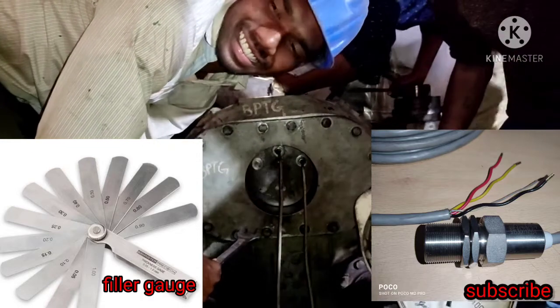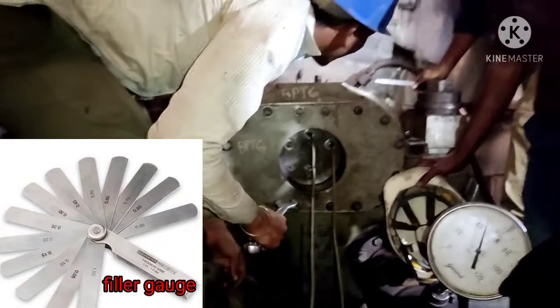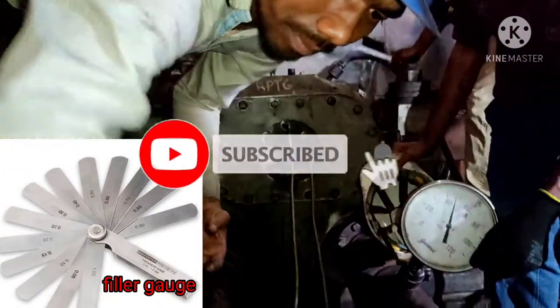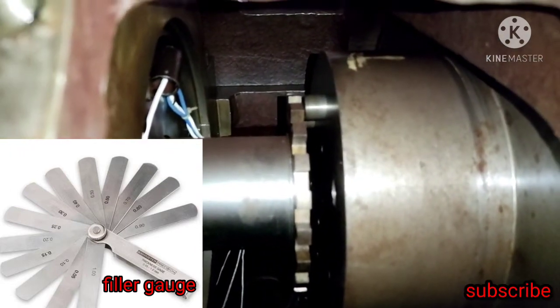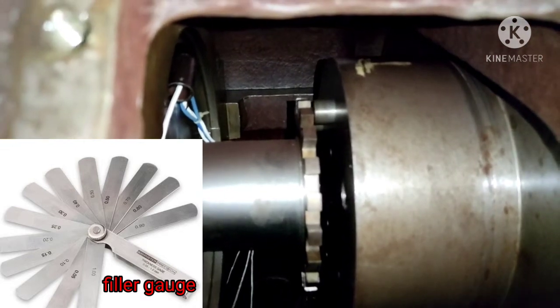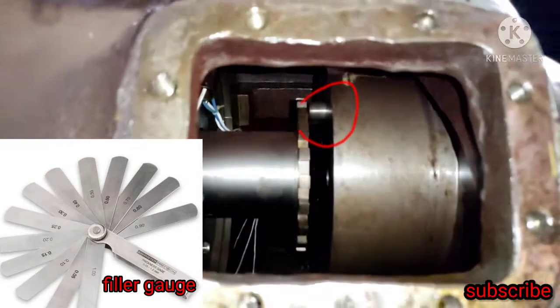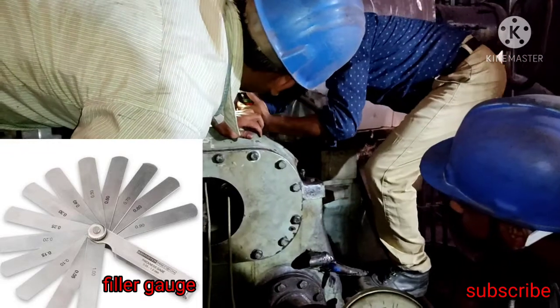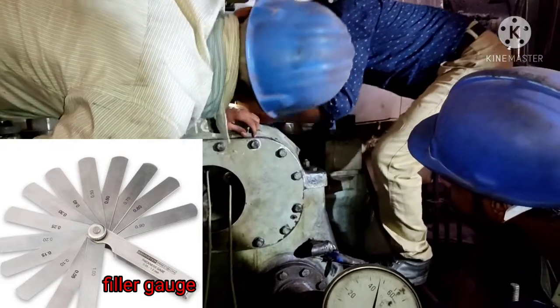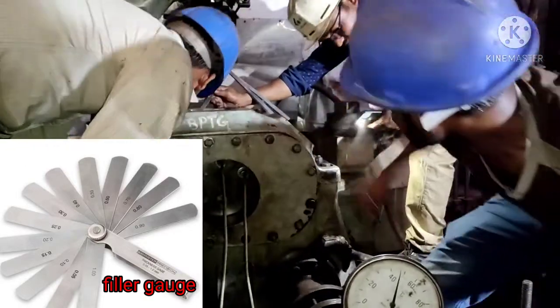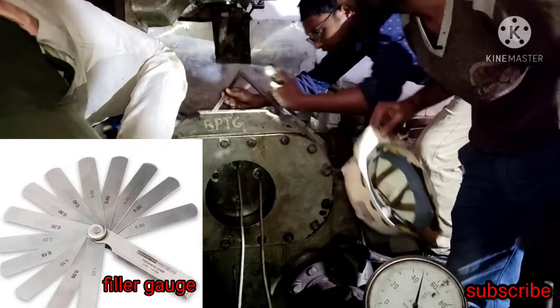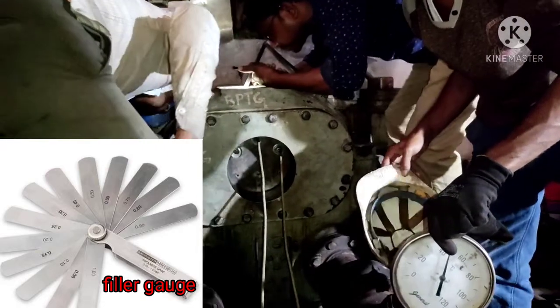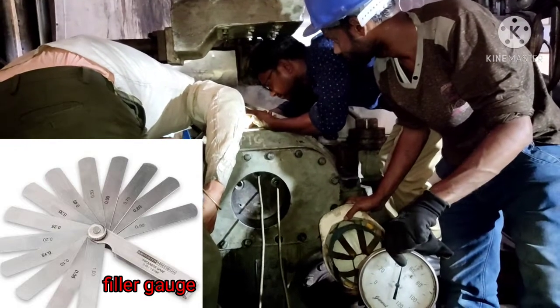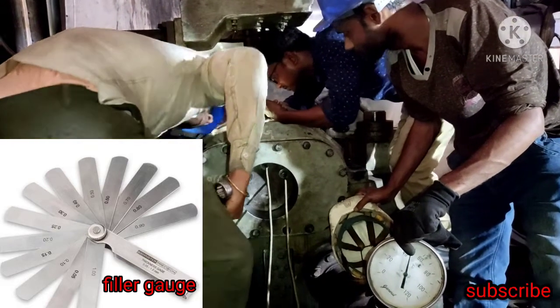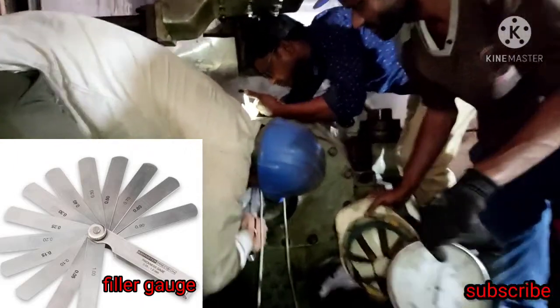According to this way, we use the feeler plate to choose and measure the gap distance. Now you are seeing that the gap between the teeth and sensor probe is very small. You cannot tell with your eyes, so we need to measure with the feeler gauge whether the distance is right or not, because we have to maintain 1.5 mm, which is the required distance.